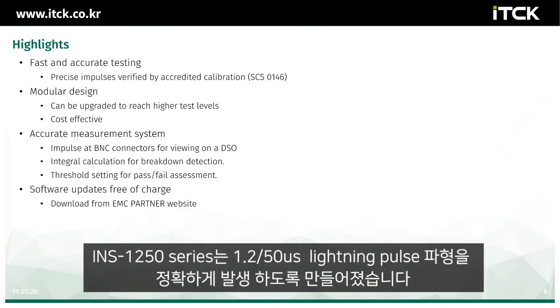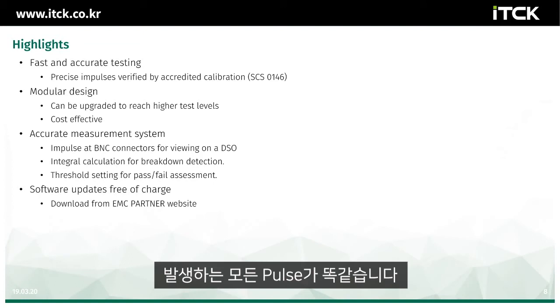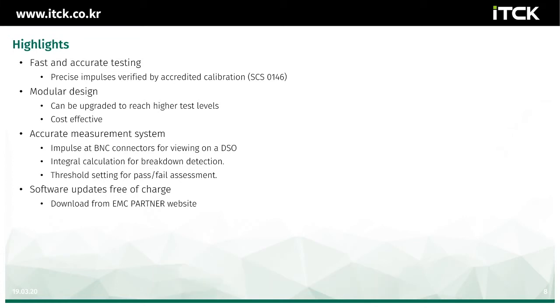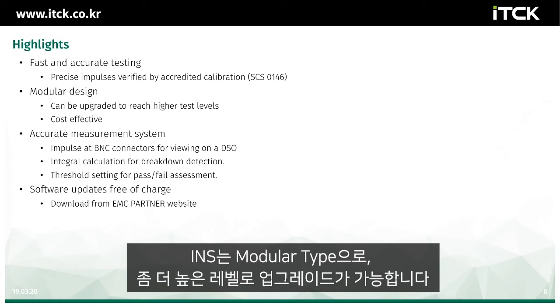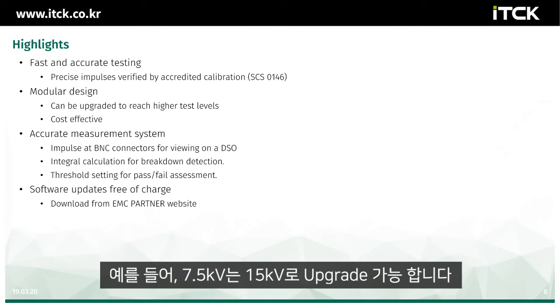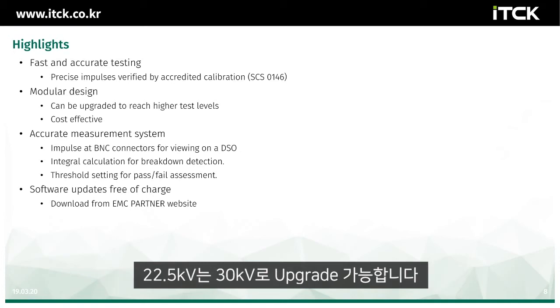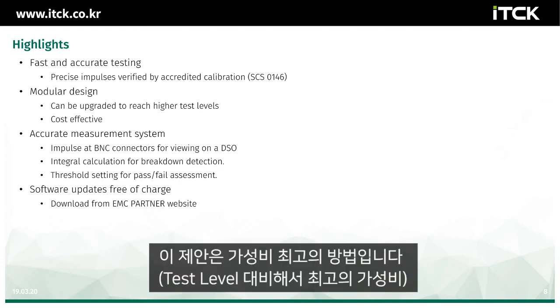Some highlights of the INS 1250 product line. The generators are designed to produce the 1.2 by 50 lightning impulse with a high degree of accuracy, so that from pulse to pulse the impulses are exactly the same. The generators are a modular design, which means that they are upgradable. So for example, the 7.5 kilovolt generator can be upgraded to 15 kilovolts, and the 22.5 kilovolt generator can be upgraded to 30 kilovolts.